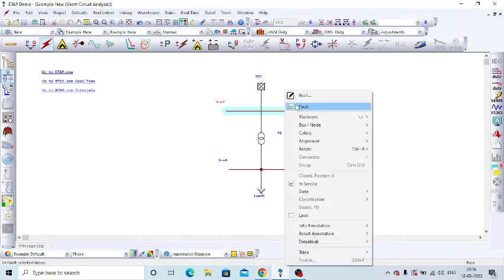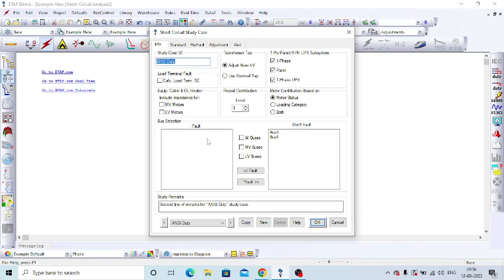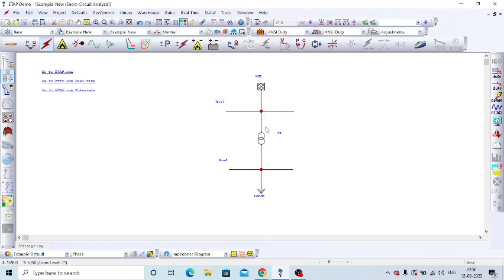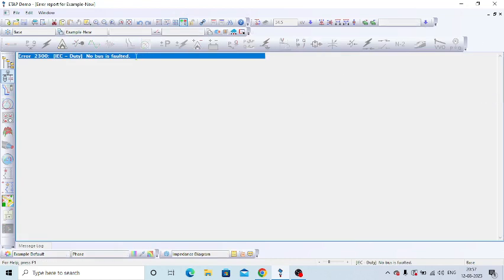We can select them one by one like this, or one more option is there in the edit study case. In the info page, the left side is the bus selection, faulted bus. These are the buses for which we are going to calculate the fault current. On the right-hand side is don't fault. At present we have two buses, bus 3 and 4. We can select these buses, and if we press fault, it will go to the bus selection page. Suppose if 100 buses are there, doing it one by one will take more time. In this way we can easily select a number of buses for the fault studies. So now I selected the two buses. Okay, so just run IEC 60909. No bus is faulted.